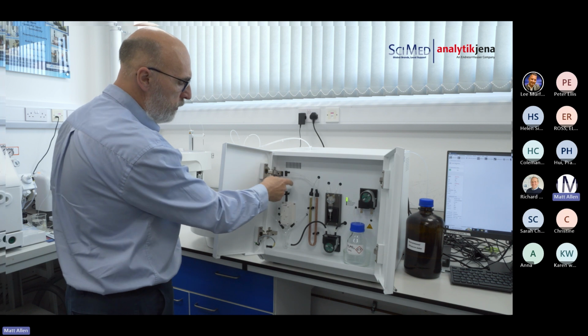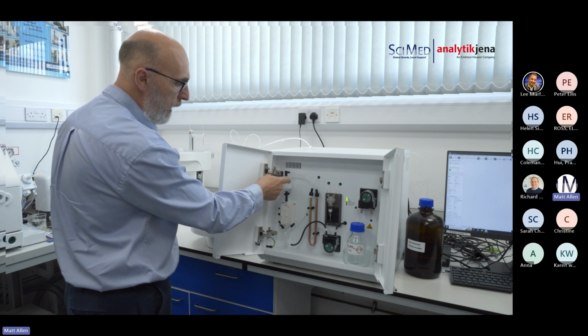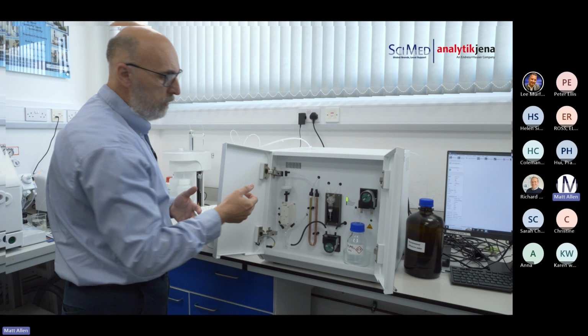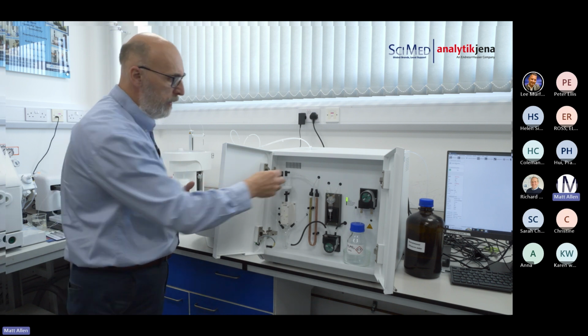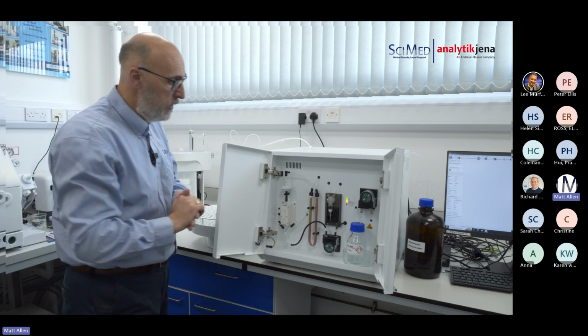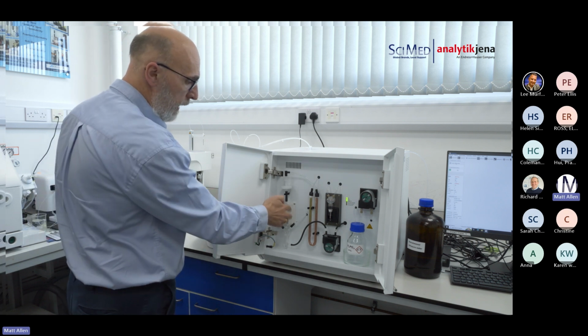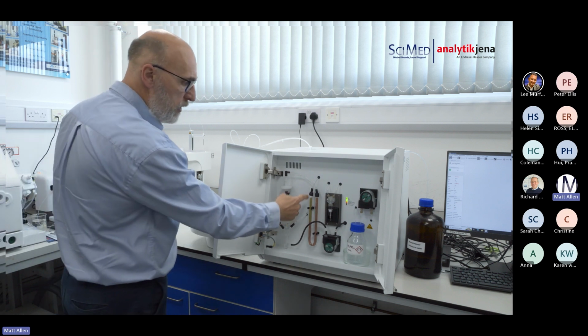It comes through two different traps here. We have a water trap and a particulate trap. They can both be exchanged very, very simply. Pop the top off, replace. Might be done every few months, or again, depending on throughput, at the annual preventive maintenance visit. We have a Peltier cooler here for the inorganics chamber if we're doing TOC by difference, or maybe just measuring TIC. We have a halide scrubber.